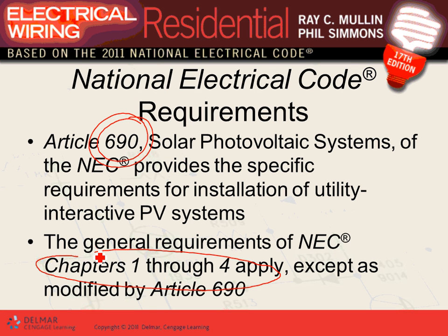As you bring, like, our system here, we put a 2-inch EMT conduit. We brought it all the way to the lab. We put conductors in it. Which rules apply to all this installation? Chapter 3. So solar photovoltaic system is an electrical system. Chapter 1 through Chapter 4 in the NEC code book applies to it unless it's modified or added to by Article 690. This is everything in the code, guys. Typically, if it's a special system, the code assigns an article for it. Does it mean Chapter 1 through Chapter 4 always applies to everything electrical, with modification in its own chapter or article, like in 690?